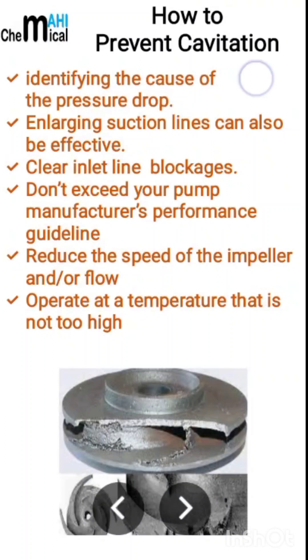Now, how to prevent cavitation in centrifugal pumps. To do that, you have to identify the exact cause of the pressure drop. Pressure drop basically happens due to unwanted bends in the line, due to different types of valves, and due to different line sizes — like sudden increases and decreases in line size.